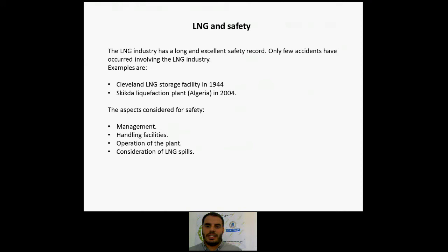Formed a vapor cloud that was ingested into the inlet of the combustion fan of a steam boiler. The hydrocarbon acted as increased fuel for the boiler, causing a rapidly rising pressure in the steam generating equipment. The rapidly rising pressure quickly exceeded the capacity of the boiler safety valve, and the steam drum ruptured, tearing apart the boiler firebox and housing. The flames from the boiler firebox ignited the leaked refrigerant gas, which was confined by the equipment and structures in the area, producing an explosion and ensuing fire.